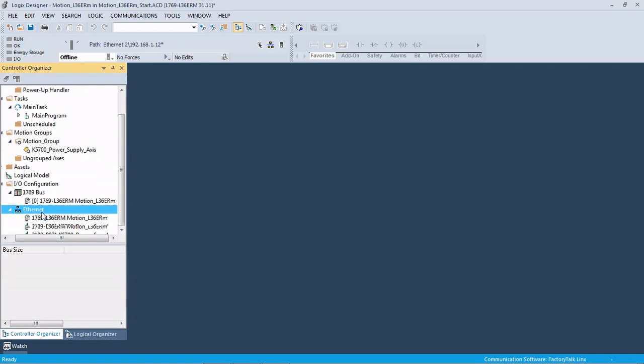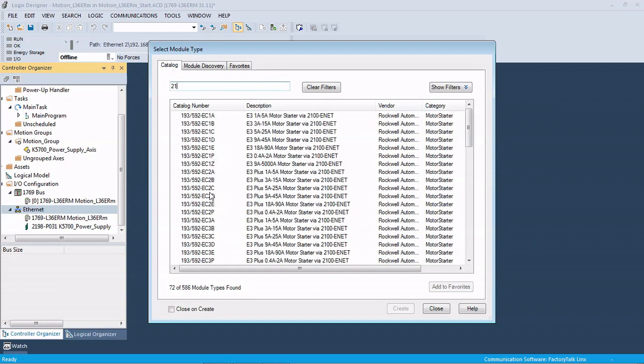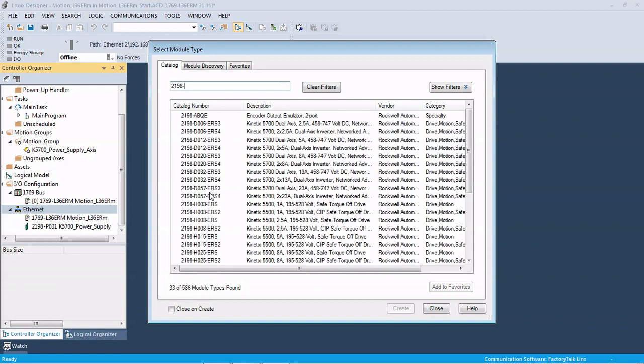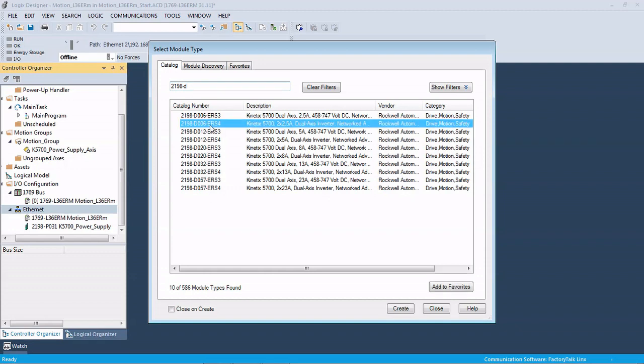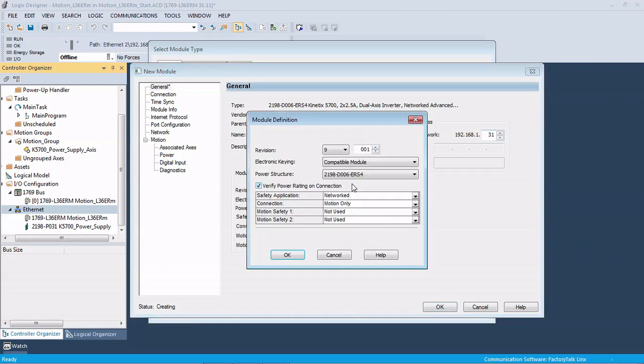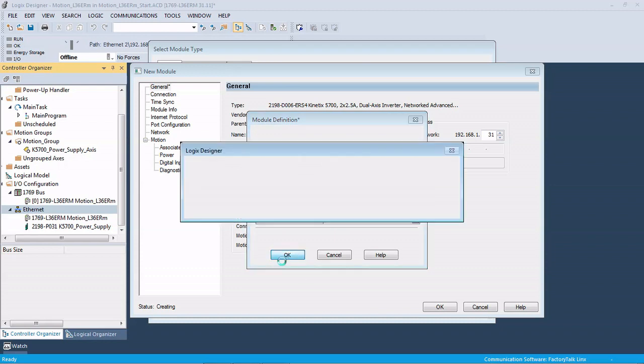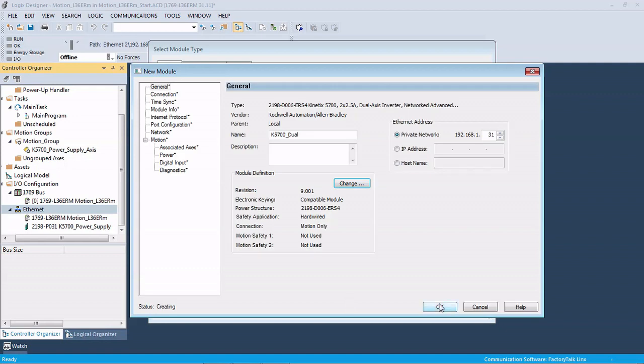Next thing we're going to come back down to our Ethernet, right click, new module. The drive we have is a 2198 D006 ERS-4. The ERS-4 has either the hardwired safety or the network safety, whereas the ERS-3 is only hardwired safety. We're going to name that Kinetix 5700 dual axis drive and give it address .31. In our situation we're not using network safety, so we're going to change this to hardwired safety.